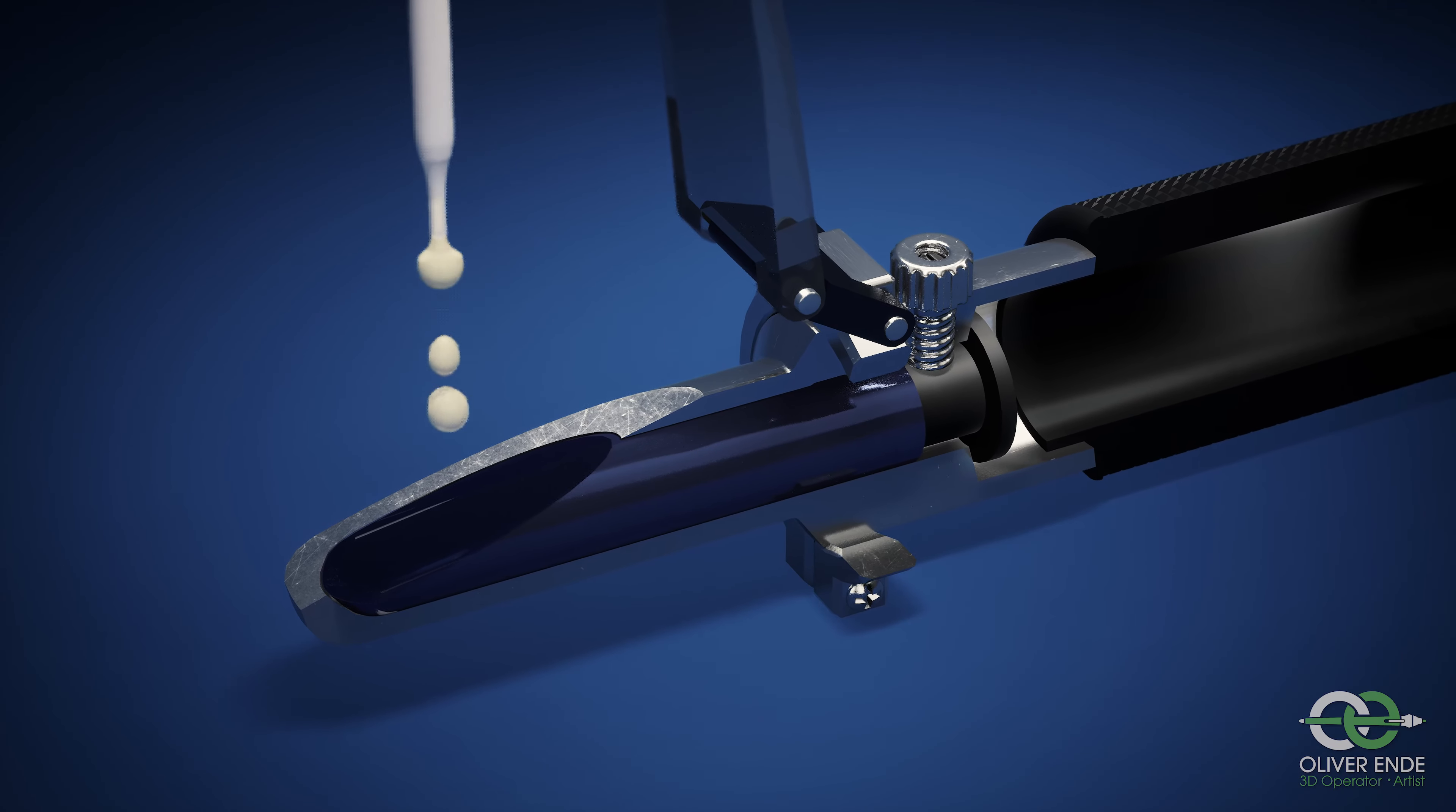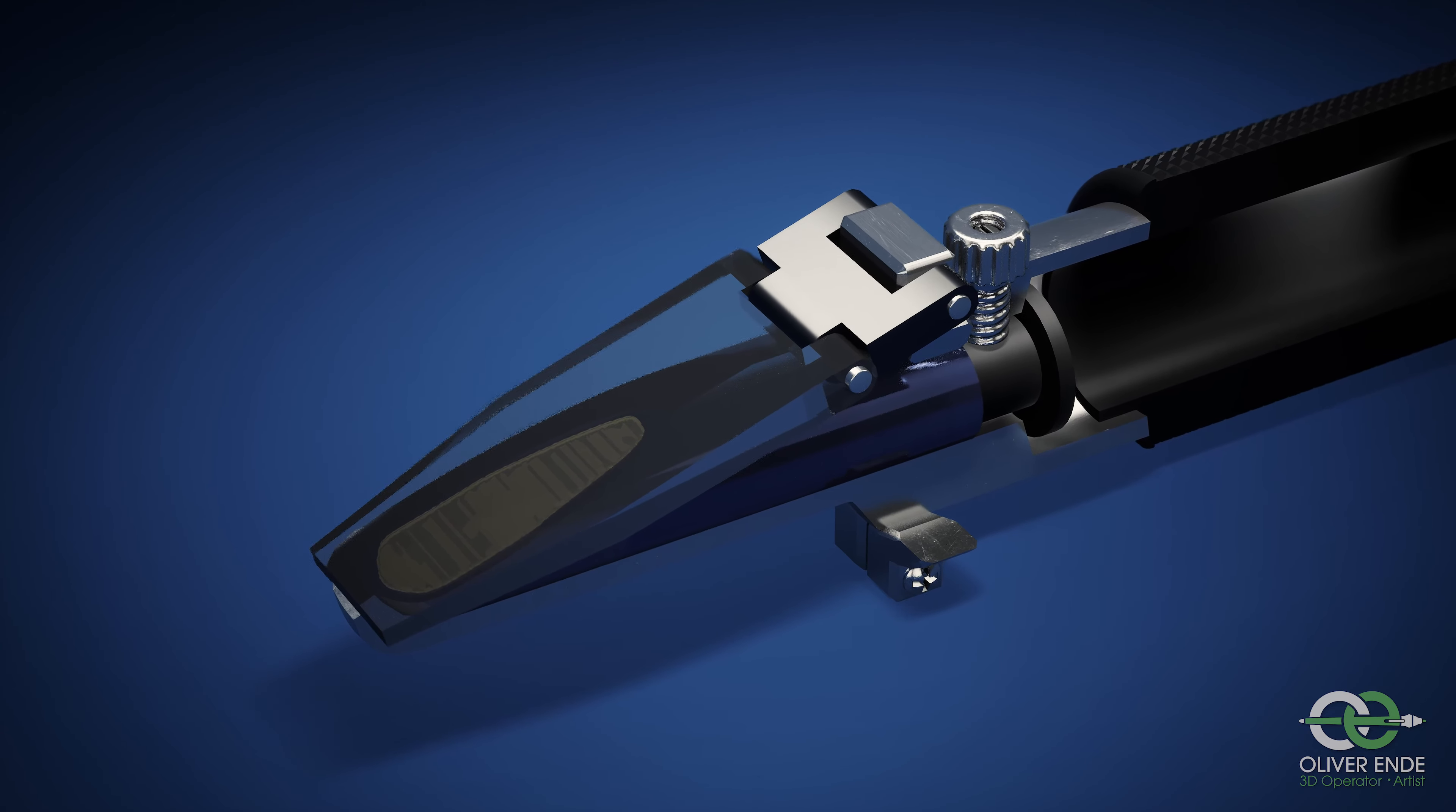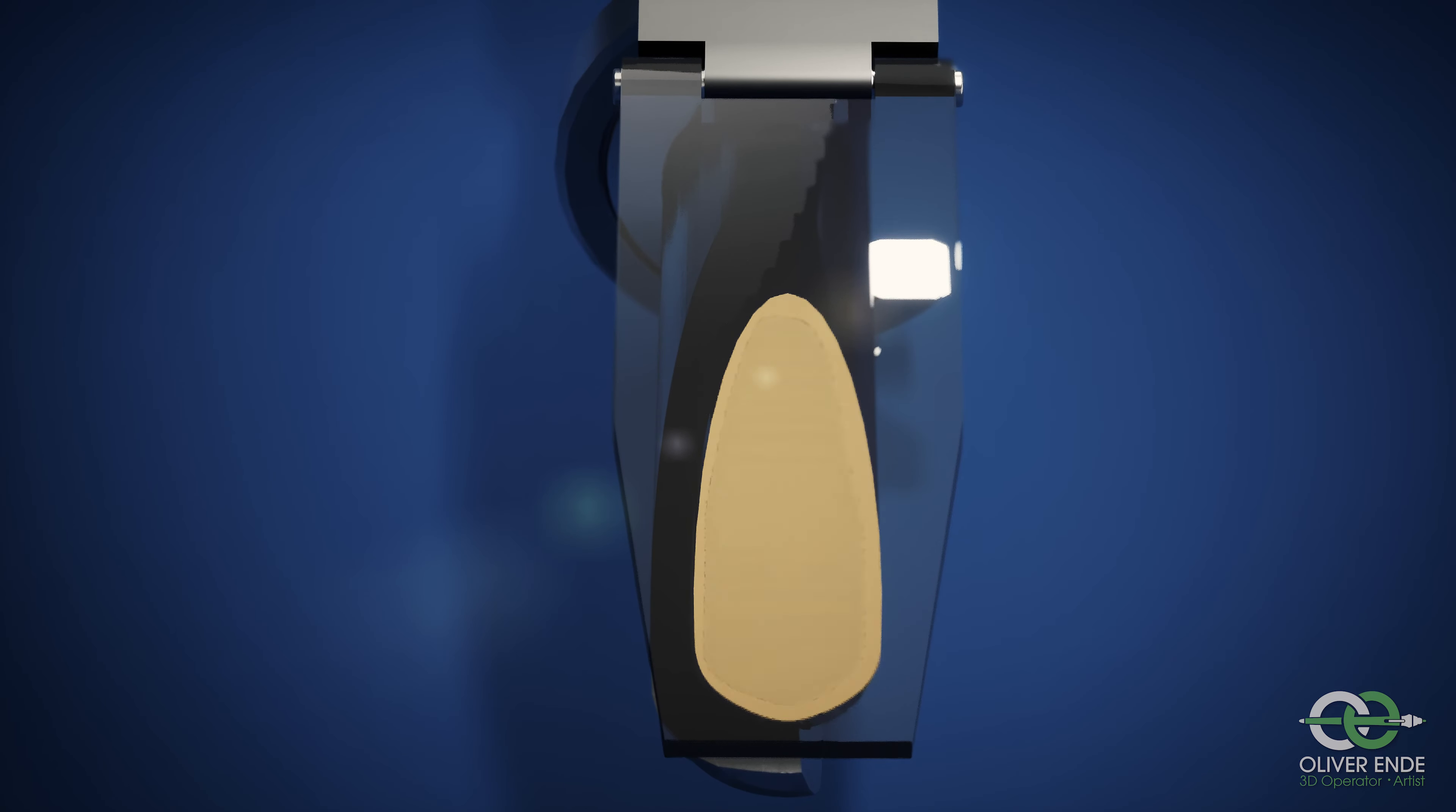After the liquid has been dribbled onto the prism, the cover is closed, which distributes the liquid evenly on the prism. It is important that the liquid is distributed over the entire prism surface because measurement errors can occur due to uneven distribution.